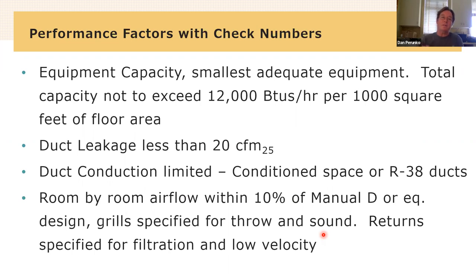These are some targets that you would work against. And again, this slide represents the outline of a day-long class. So it's equipment capacity. So you would use these as like check numbers. If I'm installing a system, I want it to not be more than 1 ton per 1,000 square feet of floor area. Duct leakage should never be more than 20 CFM total, regardless of the size of the equipment. Duct conduction has to be limited. Room by room airflow needs to be within 10% of design. You get the design from the load calculation software.